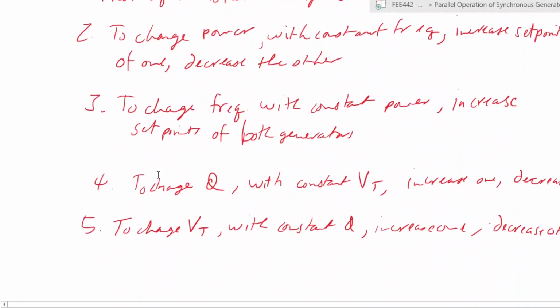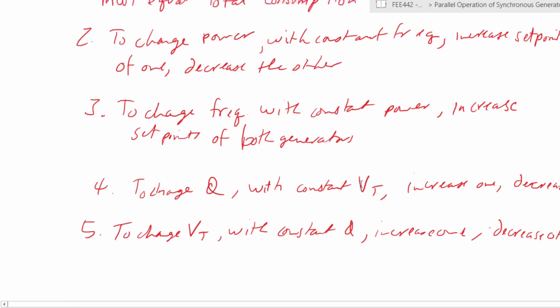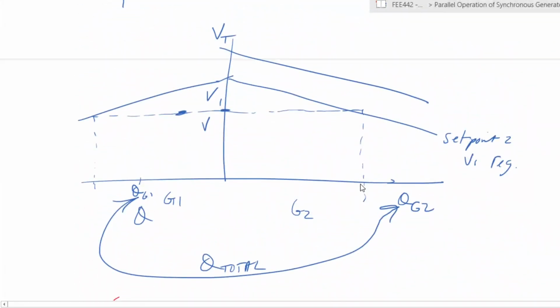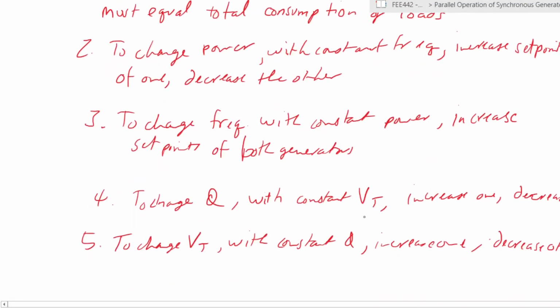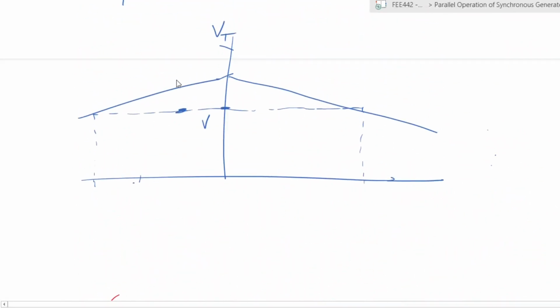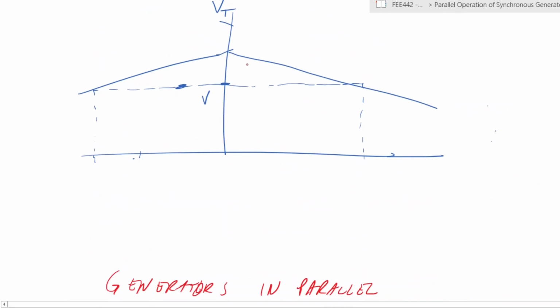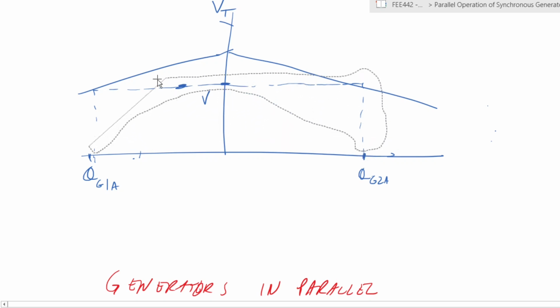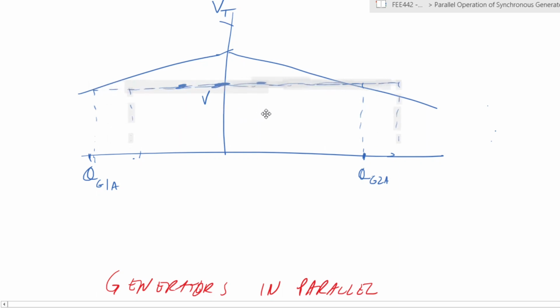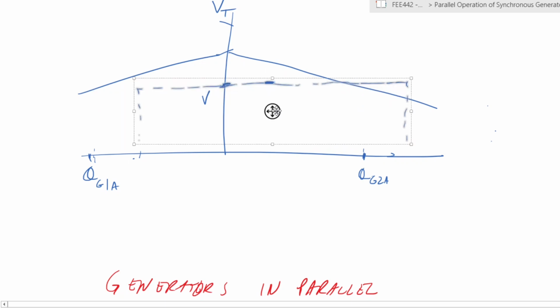So let's look at now for reactive power. So in case you want to change reactive power and retain your voltage, what do you need to do? So once again, let's clean up here a bit. I want to change Q with constant VT, right? I think let's give ourselves, yeah, okay. So this is Q. Oops. This is Q G1. This is Q G2A. That point, that point. So we want to retain the voltage at the same point, but we want to change the ratio of reactive power being supplied. So let's say we want to decrease what is being supplied by generator A. Voltage remains the same at that point.